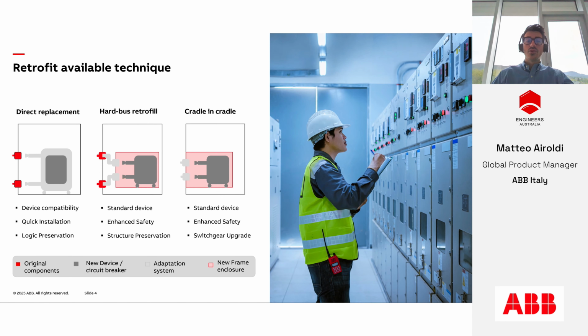The first technique is direct replacement. This is the most straightforward and time-efficient solution. It involves replacing the old circuit breaker with a new one that is mechanically and electrically compatible with the existing cradle. The key benefits are device compatibility, since the new breaker matches the original dimensions and interfaces for a seamless fit; quick installation, as no structural modifications are needed and replacement can often be completed in just a few hours; and logic preservation, since existing control wiring, interlocks, and auxiliary circuits remain untouched, reducing the risk of wiring errors and simplifying commissioning.